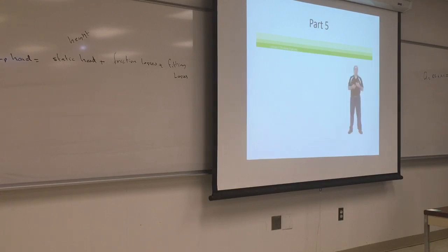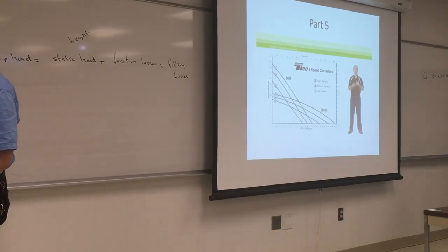Other common items include switches to change the speed of the circulator, like with the Taco 0015 three-speed service circulator. The advantage of a three-speed circulator is that it has three separate performance curves in one package. In the case of the 0015, it allows you the flexibility to dial in a specific curve to make short work of circulator replacement on a service call, since it replaces most of the commonly used circulators you're bound to find out there.